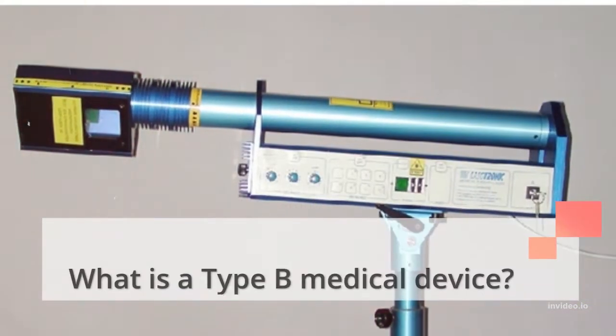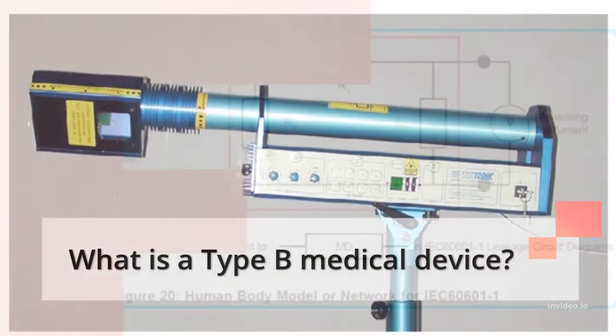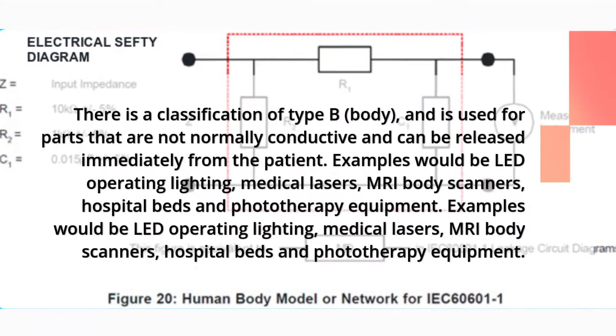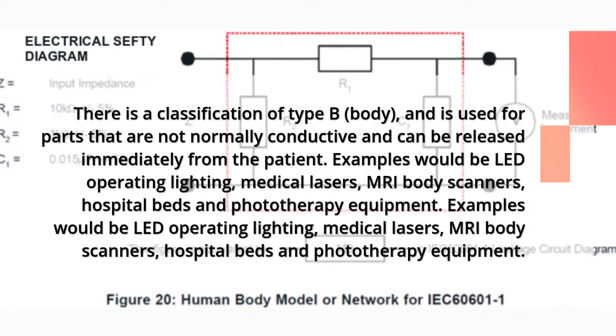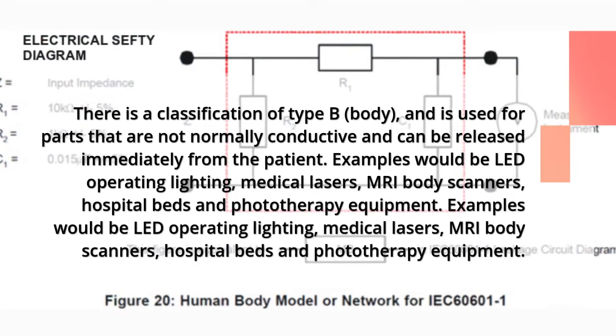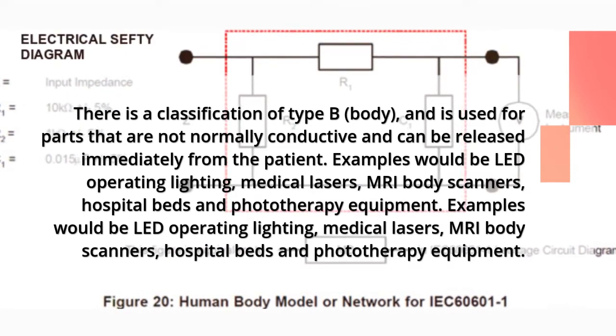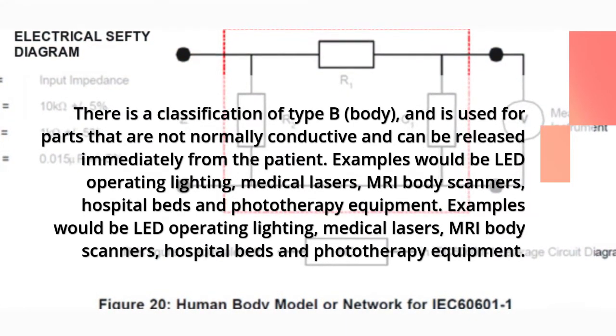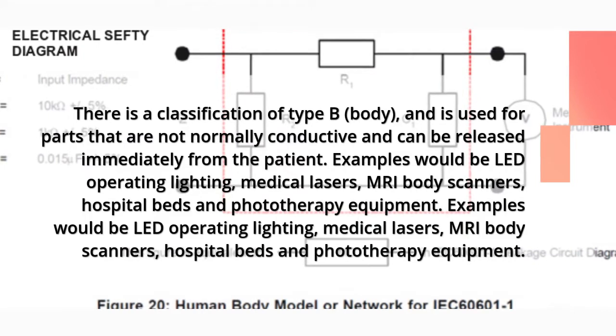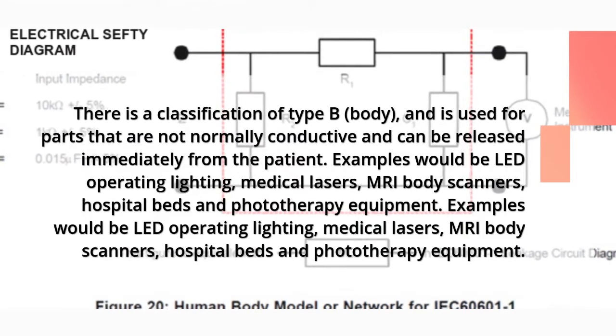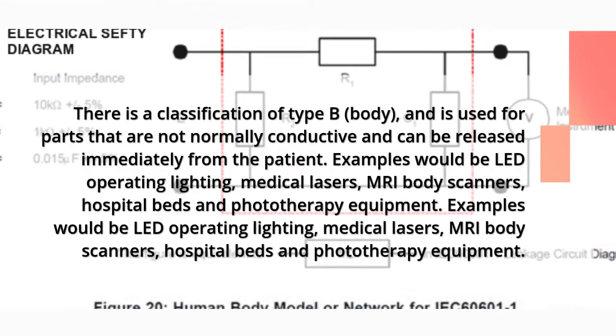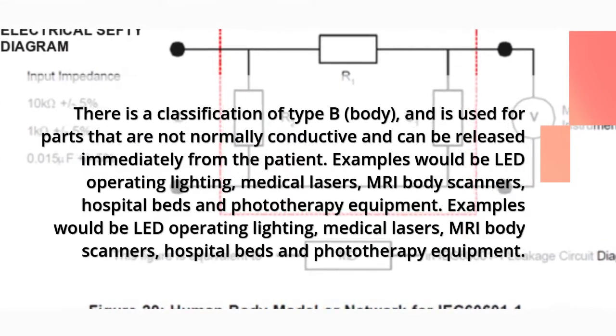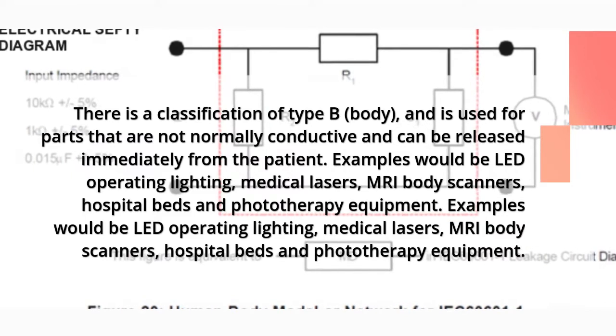What is a Type B Medical Device? Type B (Body) is a classification used for parts that are not normally conductive and can be released immediately from the patient. Examples include LED operating lighting, medical lasers, MRI body scanners, hospital beds, and phototherapy equipment.